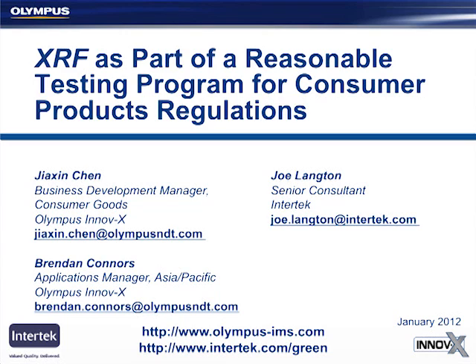It's usually best to clean your sample surface before testing, but there are a lot of cases where you can test through a very thin surface layer. So the short answer is it's better to have a clean sample to be safer, but you may find there are cases where you don't have to clean the sample based on your own testing.